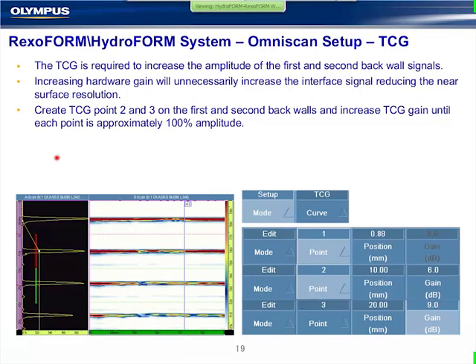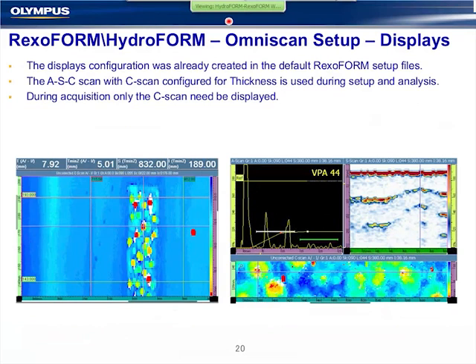If I just increase the gain, the near surface resolution here becomes poorer, and this signal increases in size. We would create a 2 or 3 point TCG. I just type in manually. I'll have an add point option, enter in the position of the first back wall, and manually increase the gain until the signal is approximately 100%. Hit add point, type in manually the position of the second back wall here. You see the little red dot, and increase the gain until the second back wall is approximately 100%. And that will result in our best results.